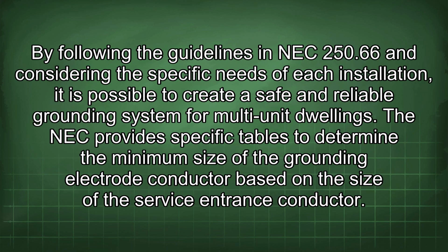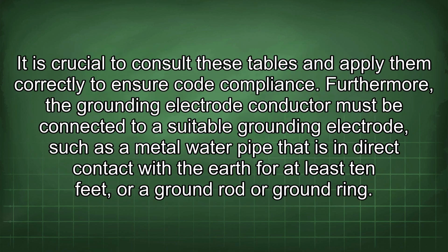By following the guidelines in NEC 250.66 and considering the specific needs of each installation, it is possible to create a safe and reliable grounding system for multi-unit dwellings. The NEC provides specific tables to determine the minimum size of the grounding electrode conductor based on the size of the service entrance conductor. It is crucial to consult these tables and apply them correctly to ensure code compliance.